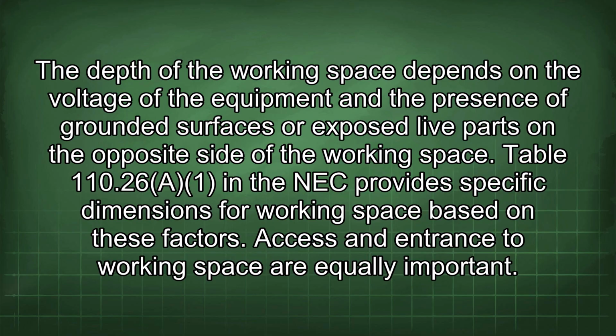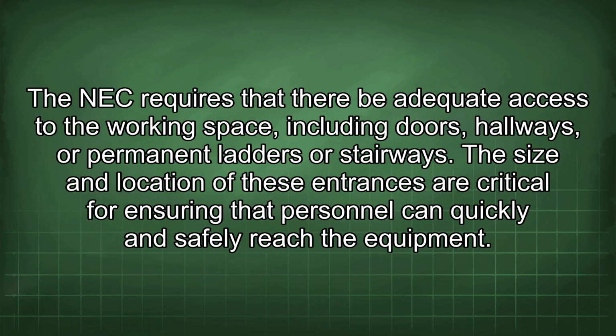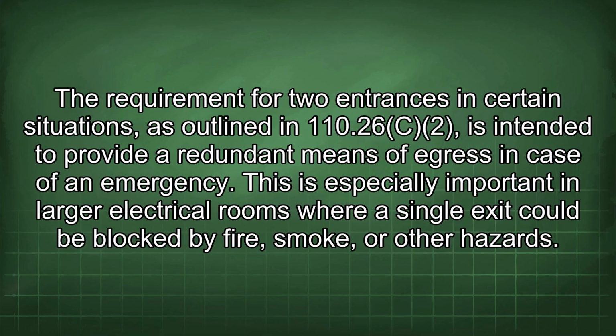Access and entrance to working space are equally important. The NEC requires that there be adequate access to the working space, including doors, hallways, or permanent ladders or stairways. The size and location of these entrances are critical for ensuring that personnel can quickly and safely reach the equipment. The requirement for 2 entrances in certain situations, as outlined in 110.26(C)(2), is intended to provide a redundant means of egress in case of an emergency. This is especially important in larger electrical rooms where a single exit could be blocked by fire, smoke, or other hazards.